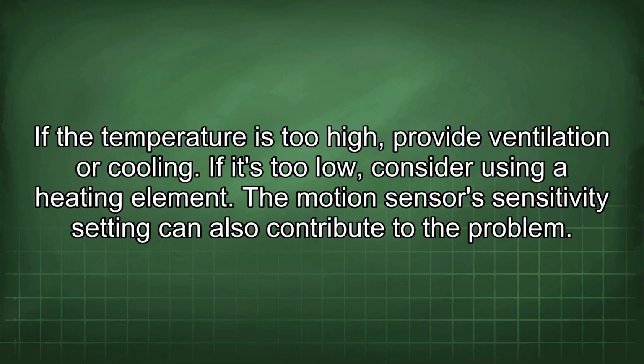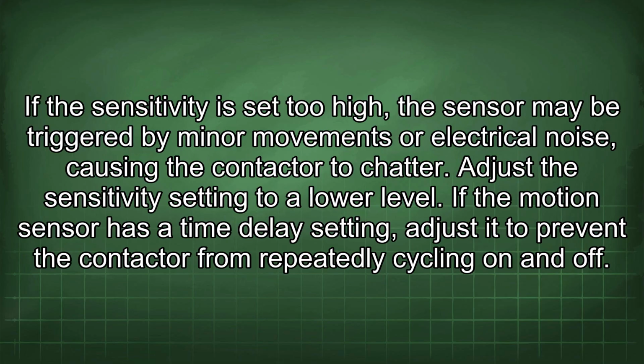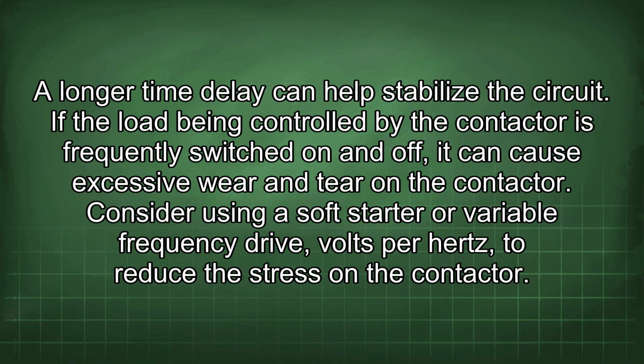The motion sensor sensitivity setting can also contribute to the problem. If the sensitivity is set too high, the sensor may be triggered by minor movements or electrical noise, causing the contactor to chatter. Adjust the sensitivity setting to a lower level. If the motion sensor has a time delay setting, adjust it to prevent the contactor from repeatedly cycling on and off. A longer time delay can help stabilize the circuit.